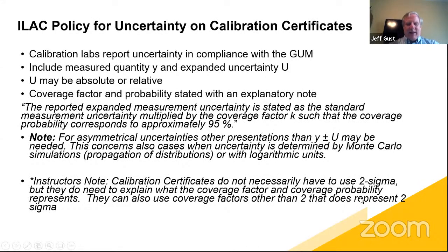And again, my note about this is that calibration certificates do not necessarily have to use a 2 sigma level. There are some laboratories that decide on my calibration certificate, I'm going to report at a 3 sigma level of confidence, because maybe they work for the Department of Energy Nuclear Weapons Complex, and they want to know their uncertainty to a 99.7% level of confidence rather than a 95.45% level of confidence. They're allowed to do that if they want to.